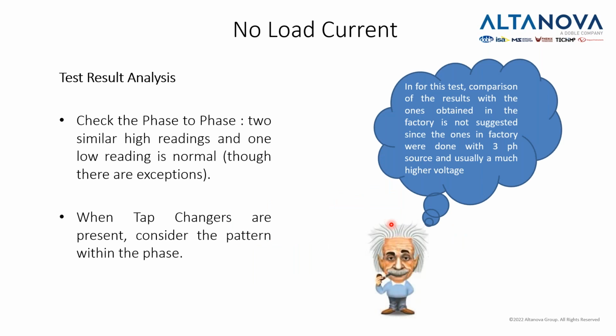So let's see what Mr. Einstein has to say. It says for this test comparison of the results, we have to take into account the fact that when this test is done in the factory, it's done with the true three-phase, and we are always getting different numbers if we compare with the testing in the field. That's why we cannot actually compare with the results from the factory.